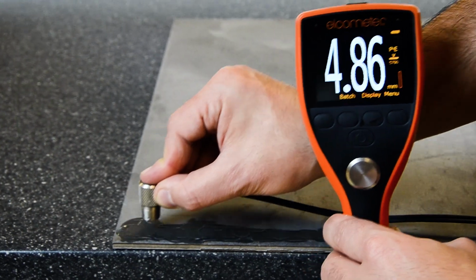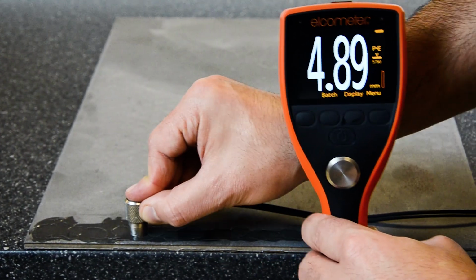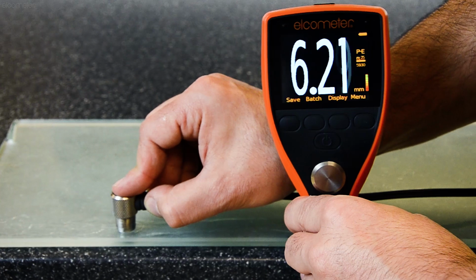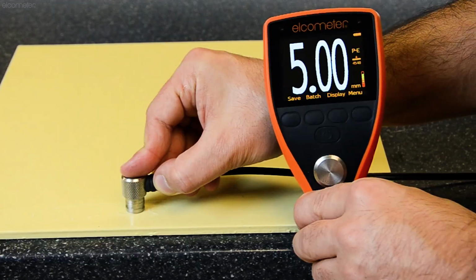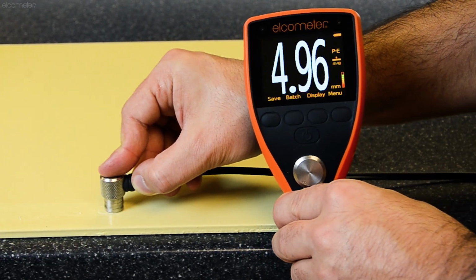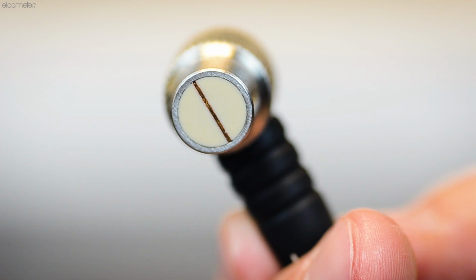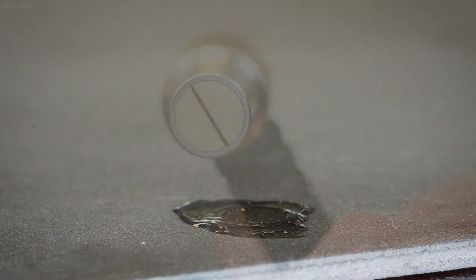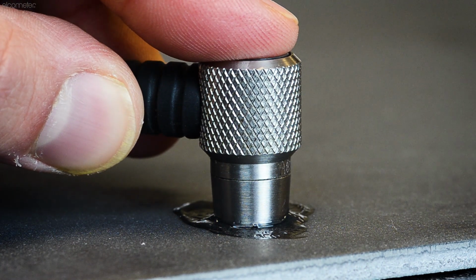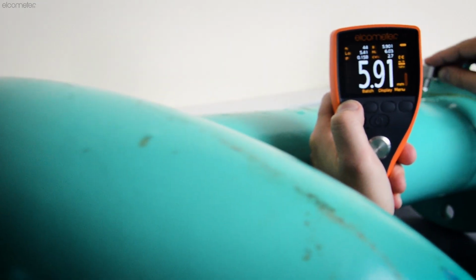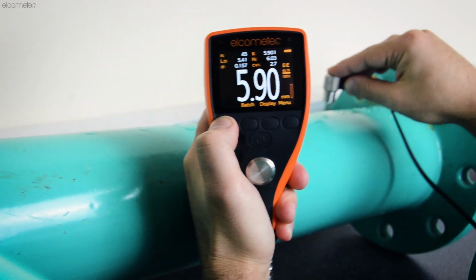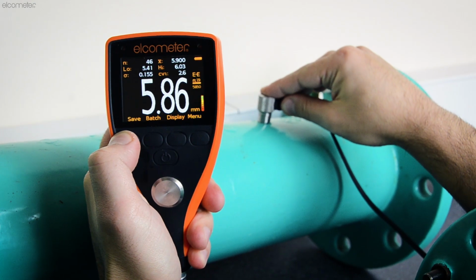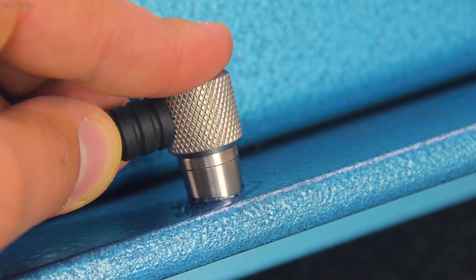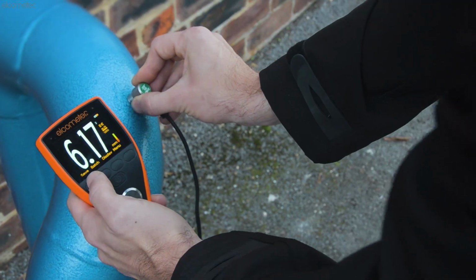With the ability to measure the thickness or sound velocity of most materials, such as metals, plastics, glass, epoxies, and ceramics, the Elcometer MTG range uses a dual element transducer and a small amount of ultrasonic couplant to measure the substrate thickness even when it's coated with up to 2 mm of paint, ideal for when you need to measure the thickness of a coated material without damaging the coating.